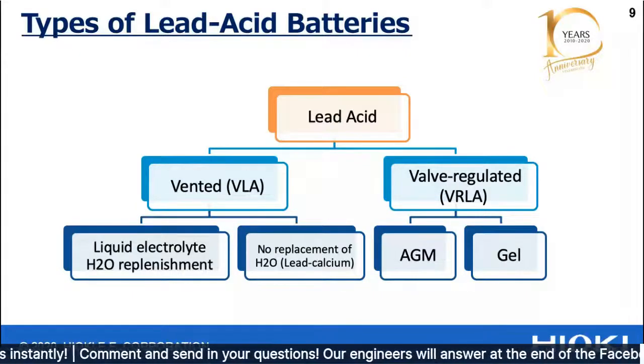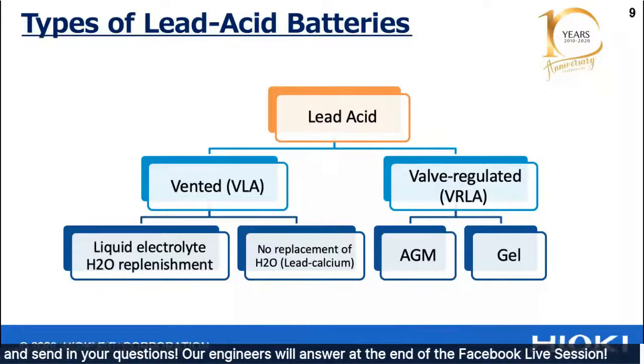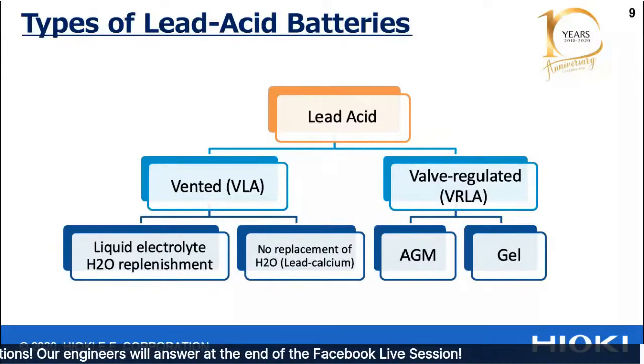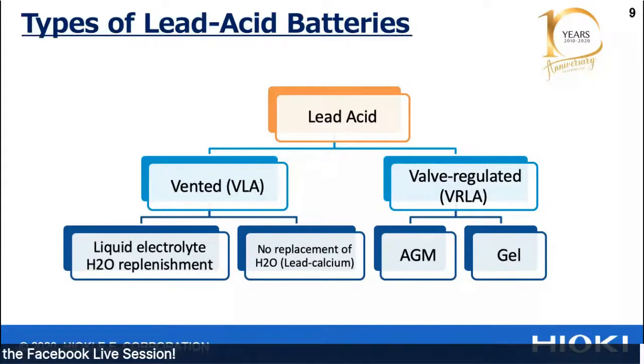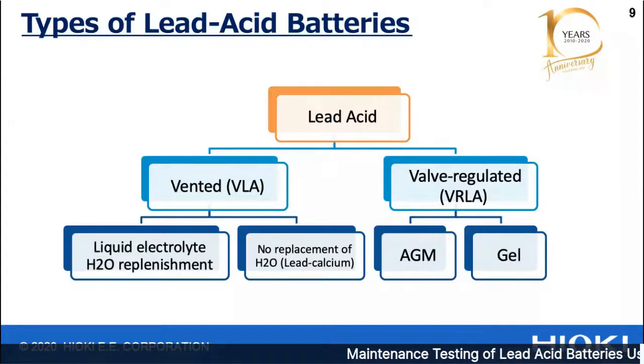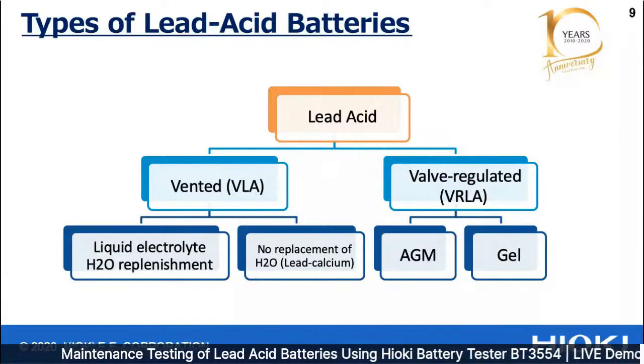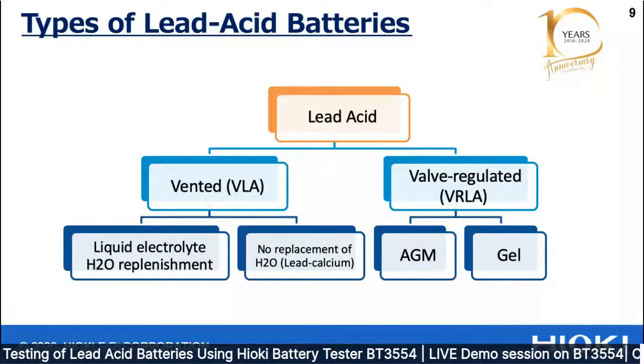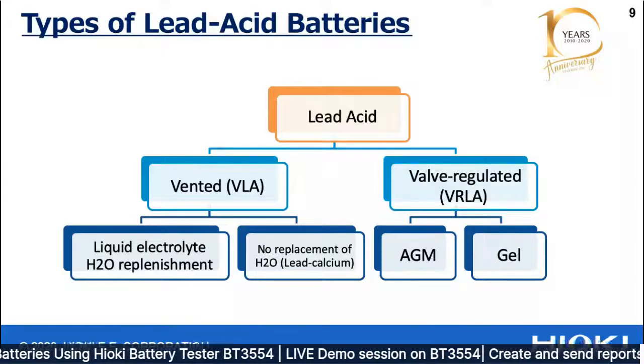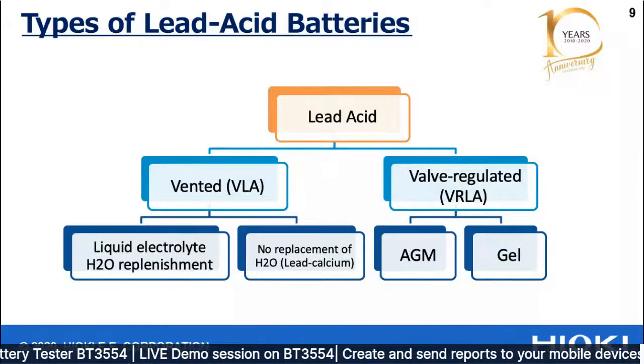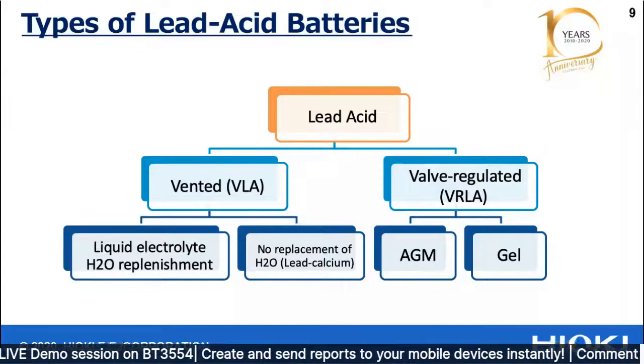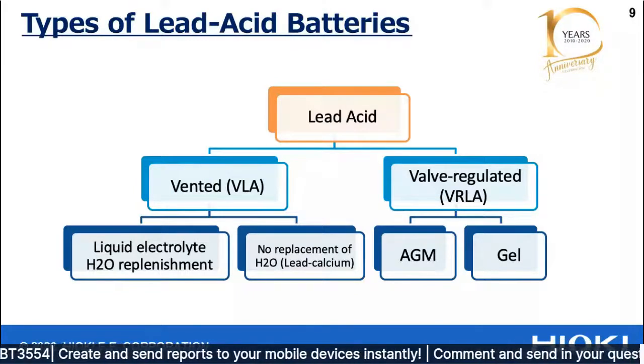Now, the VRLA, or the valve-regulated lead acids, are commonly known as sealed lead acid battery. Now, this type of battery tends not to sulfate or degrade as easily as the wet cells, the VLA types. And they are regarded as the safest lead acid battery to use. Now, there are two main versions. The first is the AGM, or the absorbed glass mat. And the second one is the gel cell, or the jellified electrolyte.